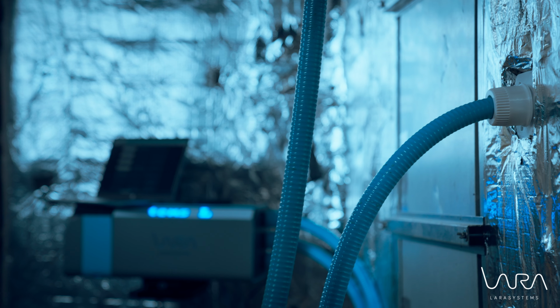The second step, mounting the Lara systems. The Lara systems can be placed in several ways. It can be mounted on the side of the air handling unit, on a wall, or even on a separately purchased mounting stand. Note: it is important that the device must not be placed directly on the ground because it draws air from below during operation. Free air movement must always be ensured under and in the immediate vicinity of the device.